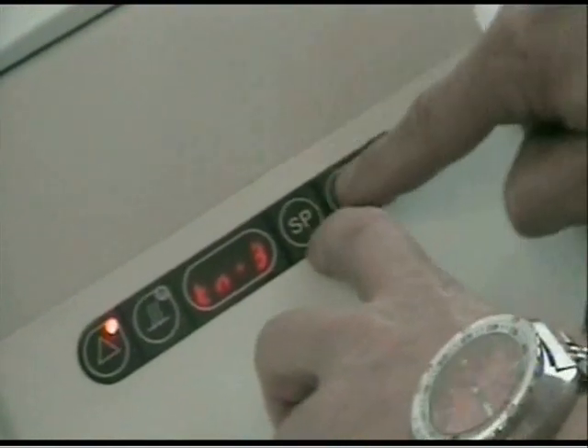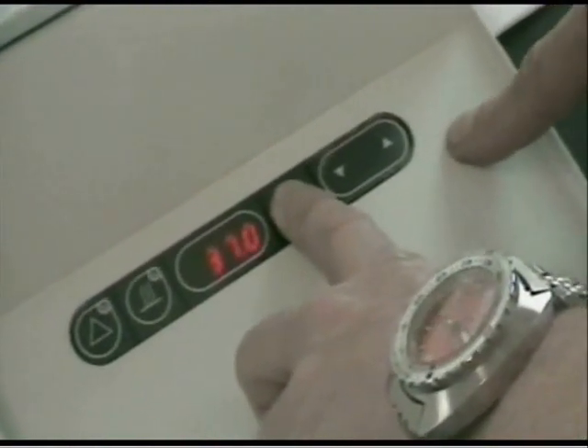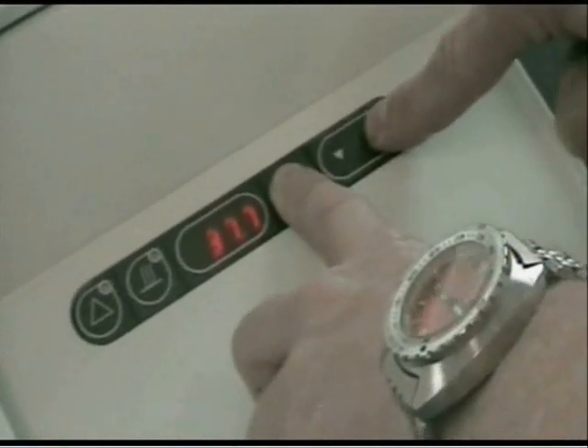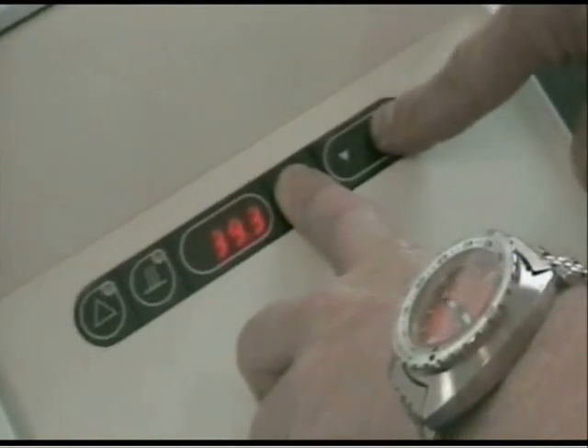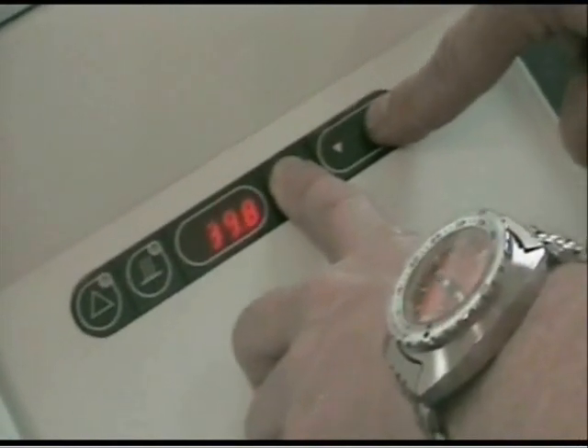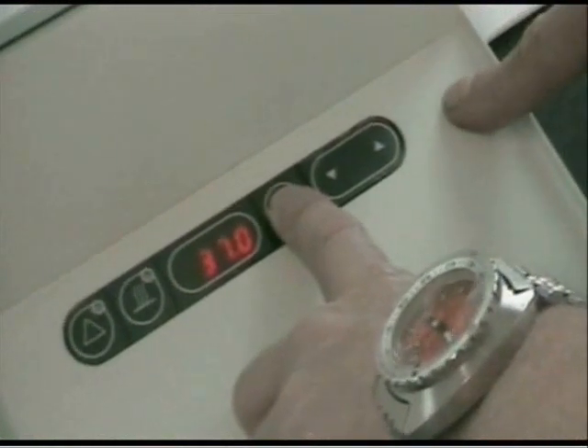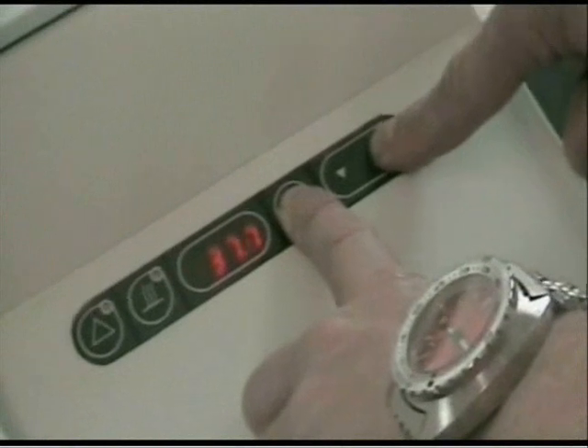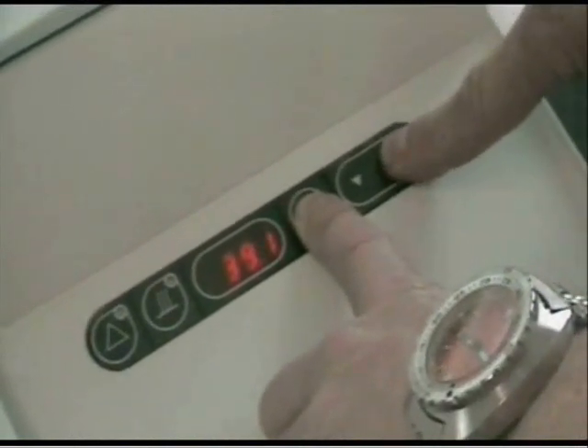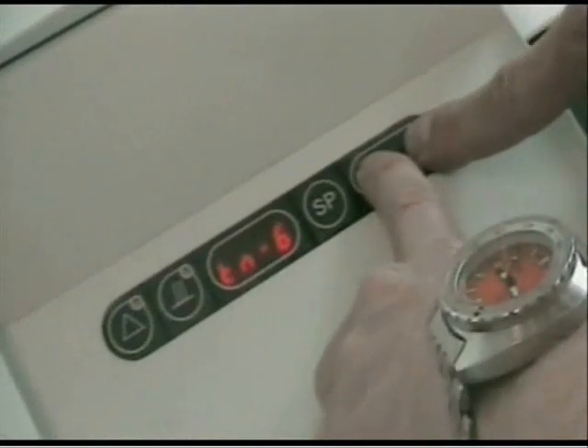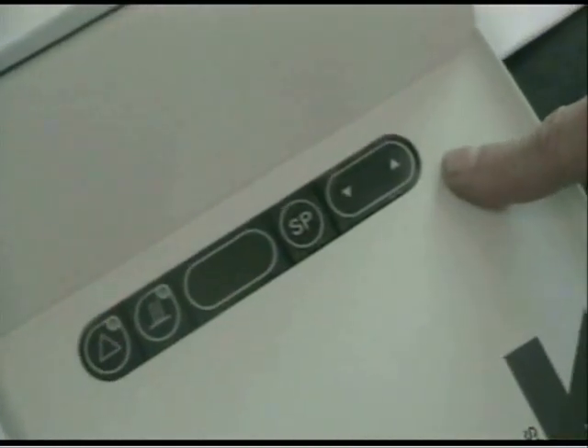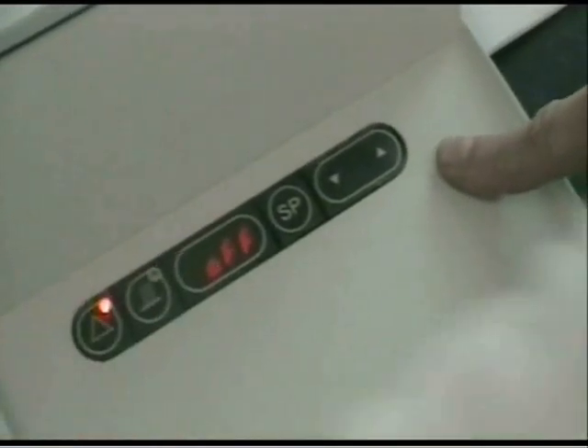Same with zone 4, which is going to be 39.8 according to our measurement. And then zone 5, which is 39.7. And then we exit the menu to store the values that we've just entered. So now we've adjusted the incubator to the first measurements that we've taken on the zones.